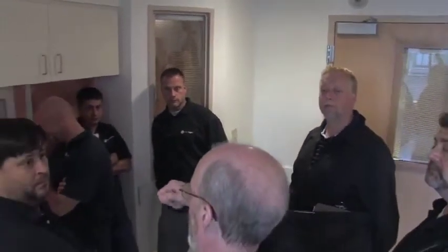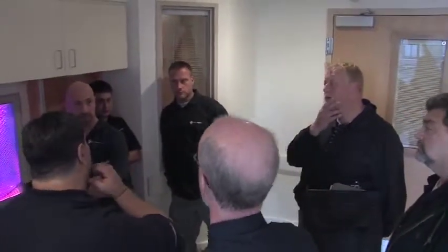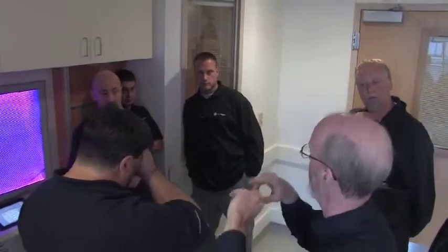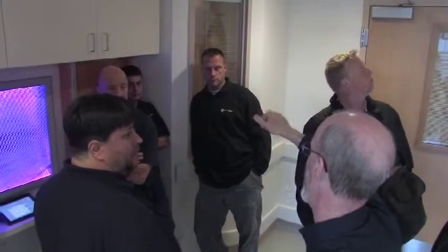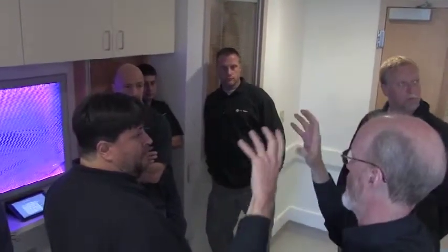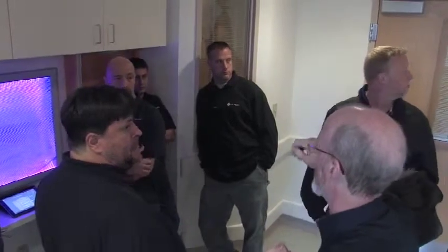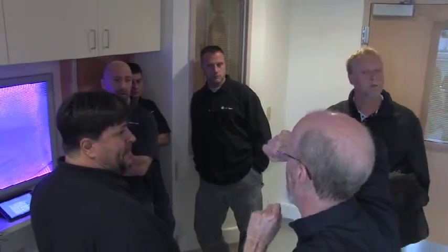There's pots on there you can adjust. Just being honest, a screwdriver for the speed. That's the pneumatic room you're talking about, right? No, some of the newer technology fan power boxes don't have the old ones, like a speed switch on the side, or a rheostat or something. A lot of them, you just open up, there's a circuit board in there. There's little tiny potentiometers in there, and you can use a little screwdriver to adjust the fan speed up and down.